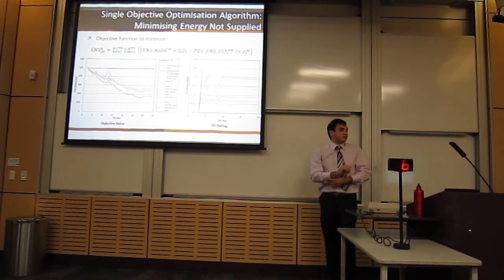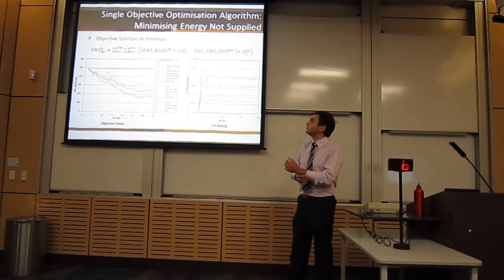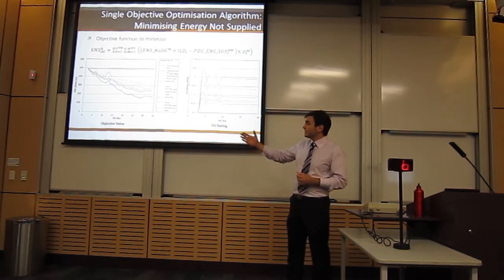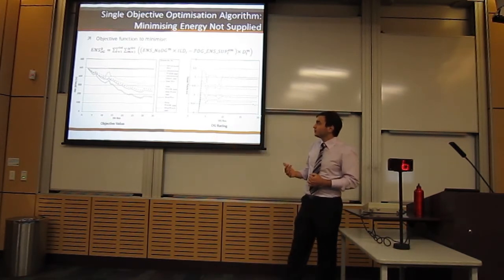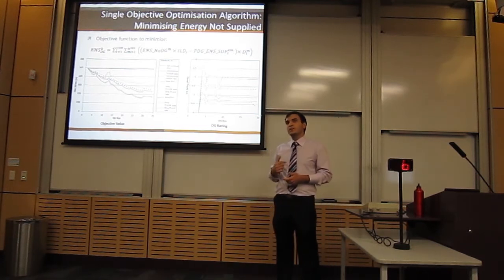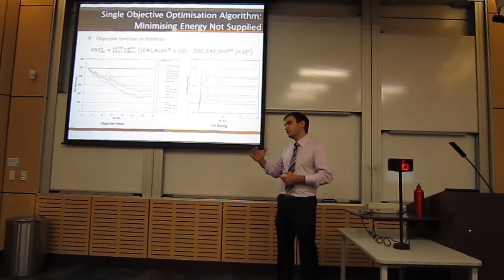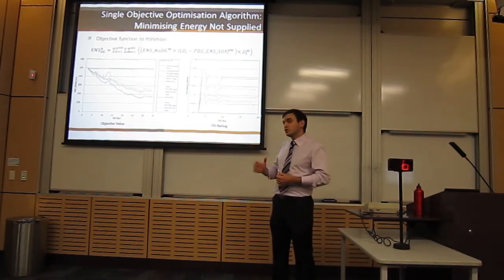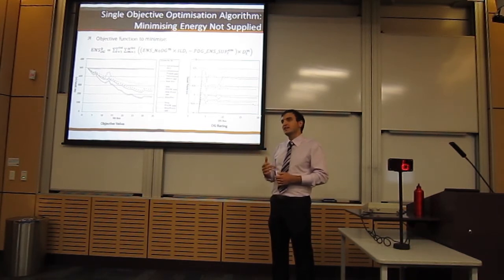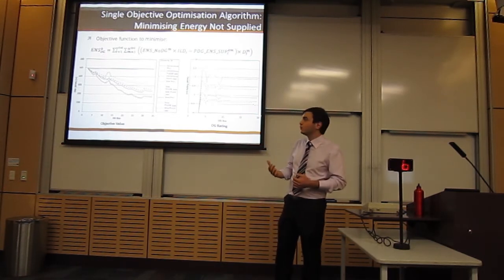The second optimization algorithm developed is that to minimize energy not supplied (ENS). As seen on the left graph, as the DG is implemented further from the grid connection, there are significant reductions in total ENS. This is because the DG can supply power to the isolated section of the network in a greater number of fault scenarios when implemented further from the grid connection. Wind and conventional generation have the greatest effect on reducing ENS, as they are relatively consistently available throughout the day, compared to solar, which has no generation available at night.